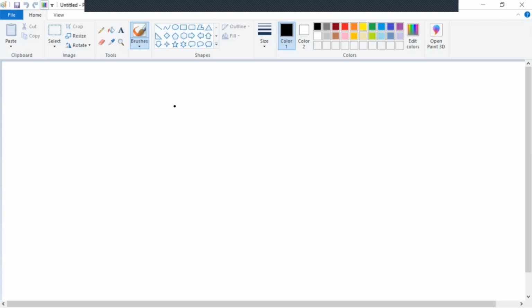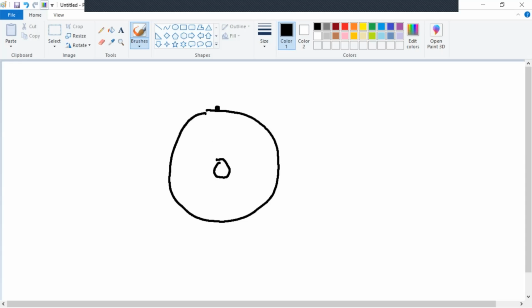Does anybody know what concentric means? Because we're going to go over two types of ground that go around a conductor. When they say concentric neutral, I'm going to draw the conductor facing down the conductor, so that the conductor core is here. When they say concentric, the ground wires, and you'll see me draw them in red here, are going around the outside, evenly spaced around the conductor. Of course, I'm drawing them freehand. That's what concentric is: evenly spaced conductors around the full diameter of the conductor cable. And it is the neutral wire, so concentric neutral.